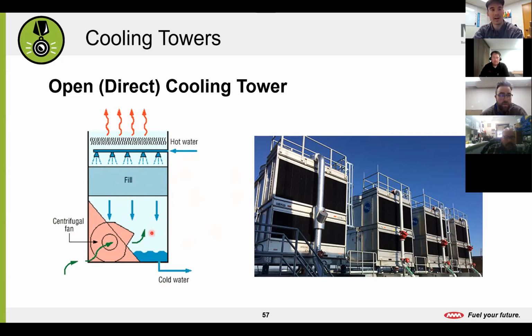The biggest downside about having an open style cooling tower is that the water that's circulating through your pipes is also exposed to the outside air. So it's exposed to all the car exhaust, just dirt, bird poop, anything you could think of that could possibly get into that water, gets into that water, and you've got to clean them a lot, and they are gross. You have strainers that fill up. You can run into situations where the strainers aren't catching 100% of stuff. So then all that sediment and debris goes down into your pipes, then starts clogging up other strainers in your building.